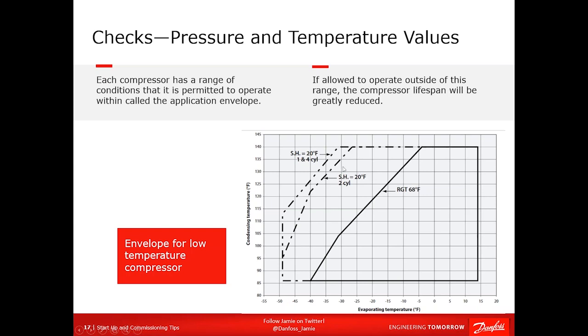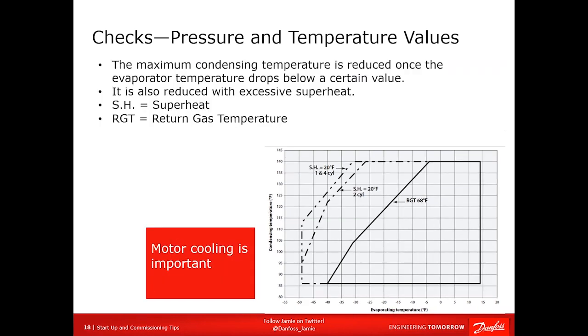Loss of charge puts you somewhere over here with very high superheat, lower evaporator temperatures, right? And poor motor cooling. So always make sure when you set your pressure control, you set it for the actual superheat, and always minimize your superheat on low temperature applications. If you're running minus 20, 10 or 12 degrees of superheat at the compressor inlet is fine to keep it free of liquid, but minimize it as much as possible because you've got to keep that compressor cool.